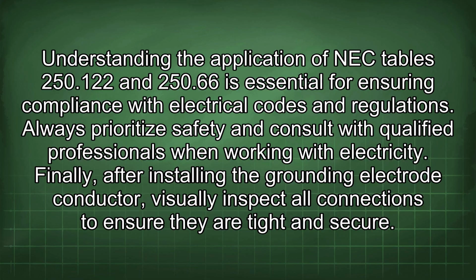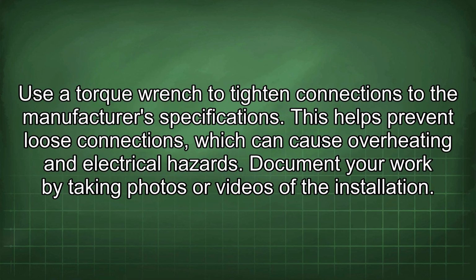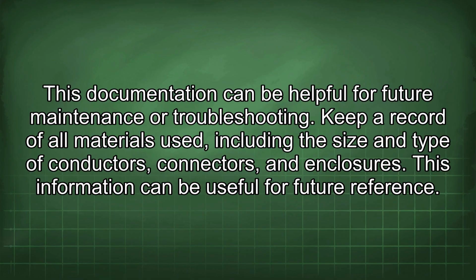Finally, after installing the grounding electrode conductor, visually inspect all connections to ensure they are tight and secure. Use a torque wrench to tighten connections to the manufacturer's specifications. This helps prevent loose connections, which can cause overheating and electrical hazards. Document your work by taking photos or videos of the installation. This documentation can be helpful for future maintenance or troubleshooting.